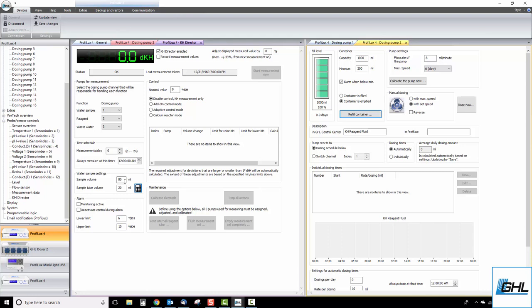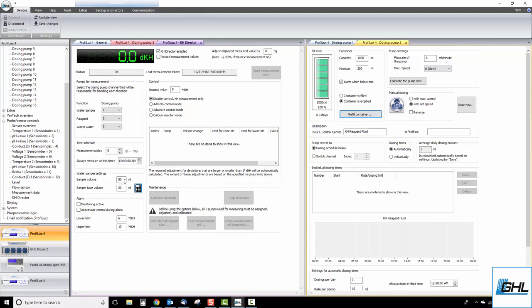At this time, make sure all your lines are properly positioned and connected. Your water sample line should be empty and placed in an area where you want the assigned pump to pull the water sample from. The wastewater line and emergency drain should also be empty and already positioned above the wastewater bin. Lastly, the KHD probe should already be installed and fastened with the compression fitting.